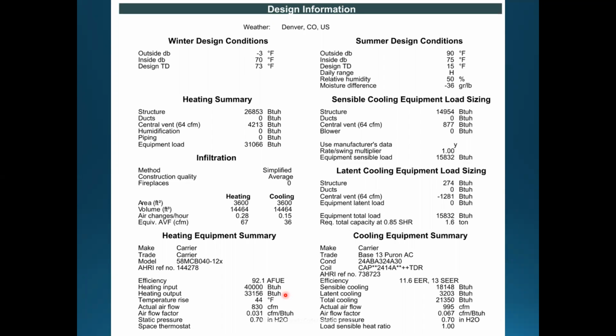So for those that are higher than 2,000 feet, this is something they actually have to do. The designer actually has to figure out what that is. Gas-fired appliance manufacturers will tell you every single time exactly what the derate for altitude is for every 1,000 feet above sea level. So in Denver, for instance, it's 5,000 feet. So it's either 2% or 4% per 1,000.